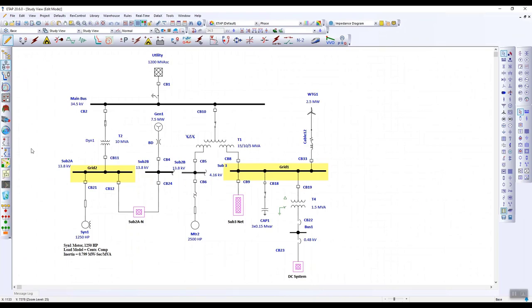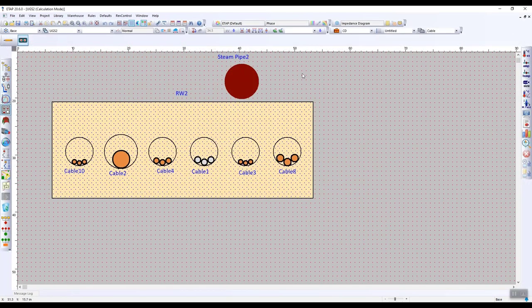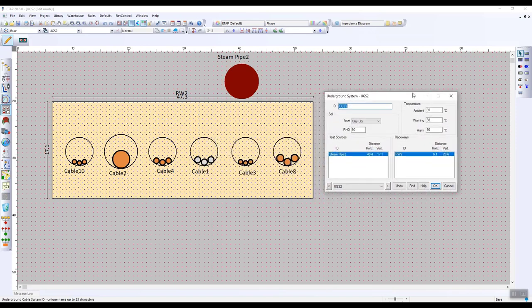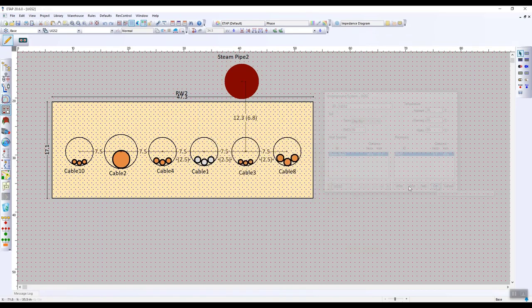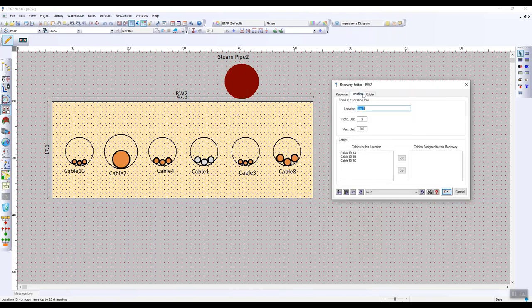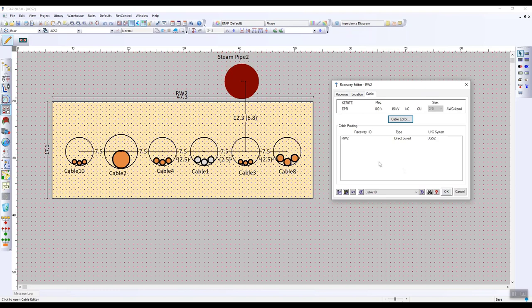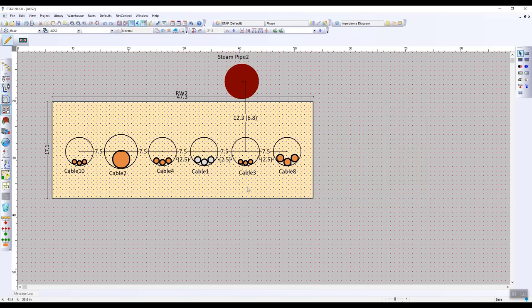Underground duct banks allows for a cable derating analysis. Specifically, steady state temperature calculation, uniform ampacity calculation, uniform temperature calculation, cable sizing, and transient temperature calculation. You can specify the soil type surrounding the raceway and the soil type inside the raceway. You can also specify the location of the conduit and also open up the cable editor if you'd like to make additional changes to the cable.